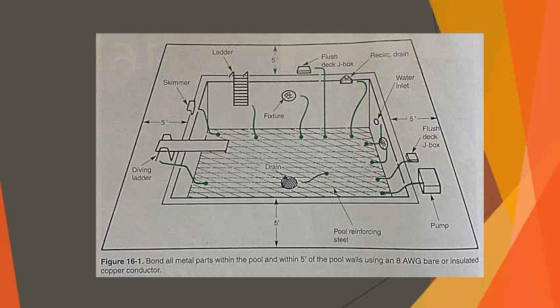These stray currents must be kept at earth potential, which is zero. The bonding of all metal parts accomplishes this and is therefore essential. See figure 16-1. Specifically, the following must be bonded using an 8 AWG solid copper conductor. Metal parts within 5 feet horizontally of the pool walls, including fencing, awnings, door and window frames.